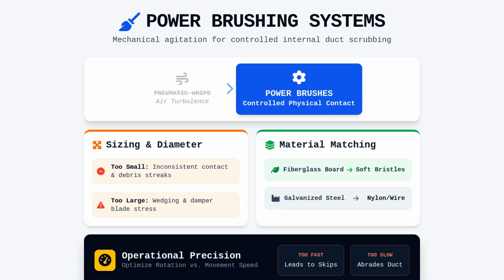Softer bristles are mandatory for fiberglass ductboard to prevent erosion of the insulation, whereas stiffer nylon or wire brushes are better suited for heavy debris and unlined galvanized steel. Operating these brushes requires careful attention to the rotation speed and movement speed. Moving too quickly through a run leads to skips, while dwelling in one spot for too long can abrade the duct material.